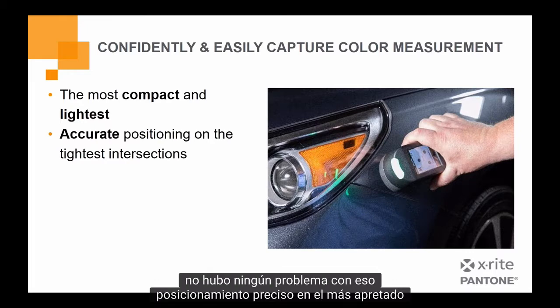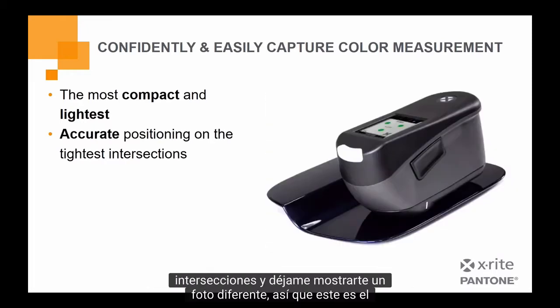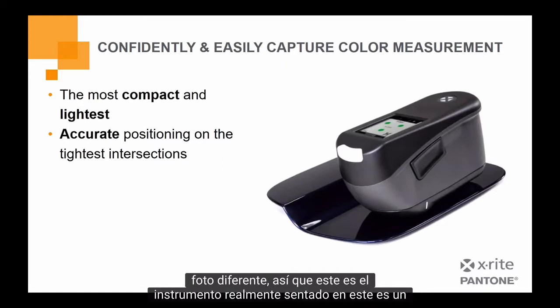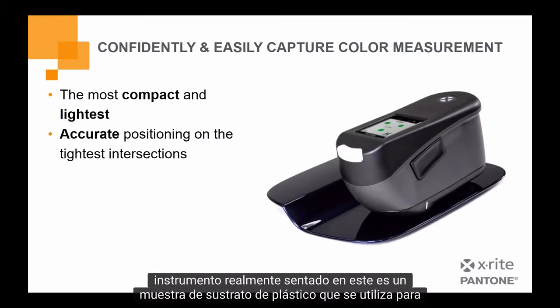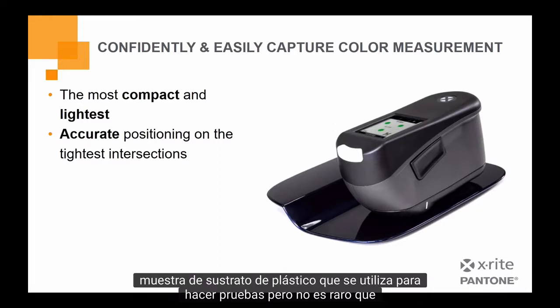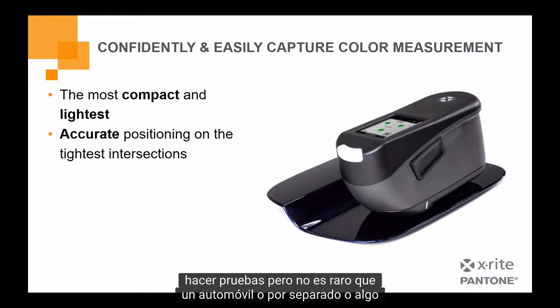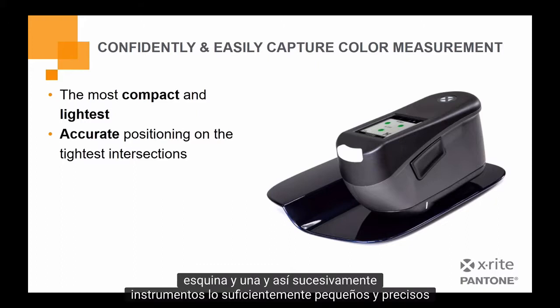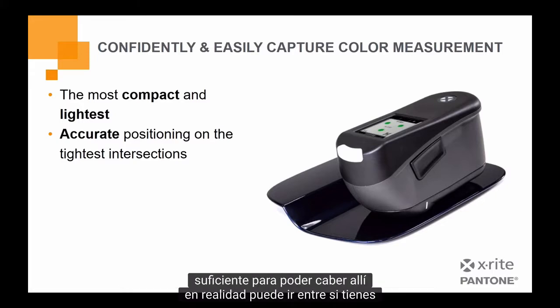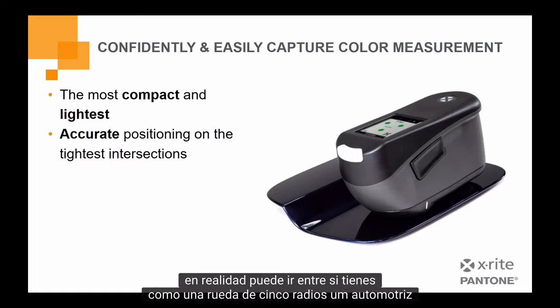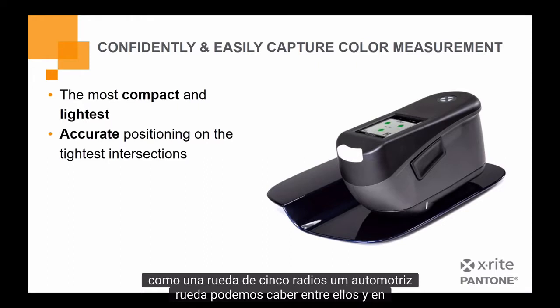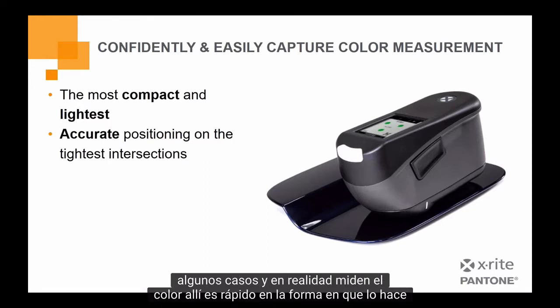Accurate positioning on the tightest intersections, and let me show you a different photo. So this is the instrument actually sitting on a sample plastic substrate that's used to do testing on, but it's not uncommon for an automobile or for a part or something you're measuring to have those kinds of things where it's got a bend and a corner and so forth. The instrument's small enough and precise enough to be able to fit in there. It actually can go between, if you have like a 5-spoke automotive wheel, we can fit between them in some cases and actually measure the color in there.